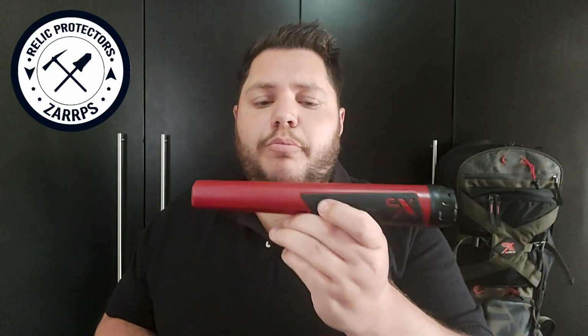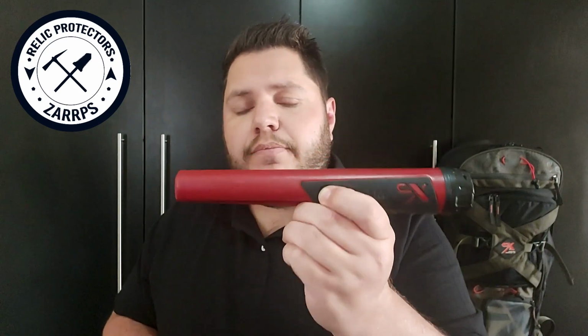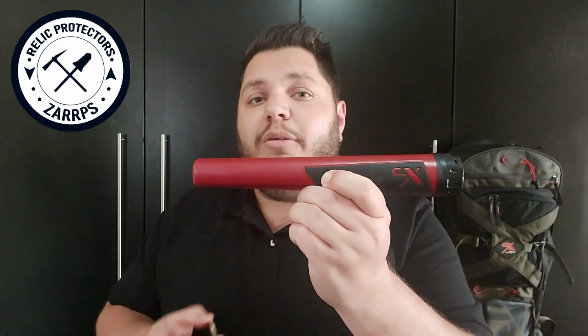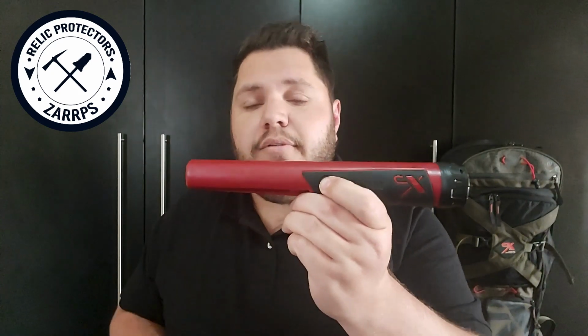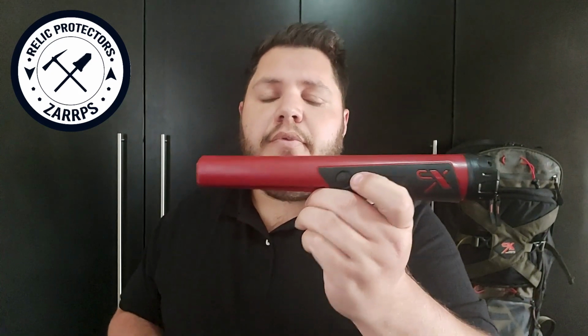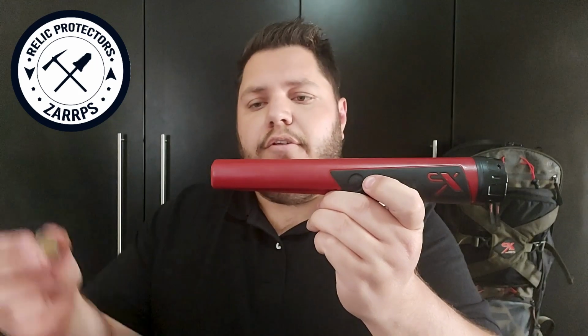Right, let's say we want to not be in the audio mode and only have vibrate and change the sensitivity settings. We'll, in the on position, enter into the second menu by pressing and holding the power button, go to the highest sensitivity in vibrate mode, which is program number 6. We press 6 times, and now we're in the vibrate higher sensitivity.